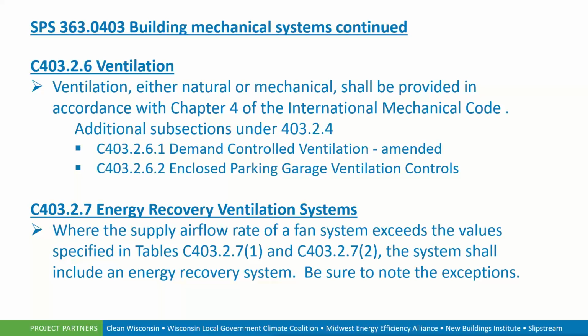ERVs, energy recovery ventilation systems, are talked about in section 403.2.7. It's where the supply airflow of a fan system exceeds the values in the tables listed in 403.2.7 paren 1 or paren 2. Those systems are then required to have an energy recovery system. I don't want to go too deep into that right now, but just be sure to note the exceptions and any footnotes on the requirements for ERVs.